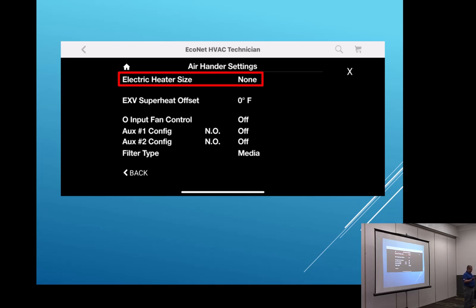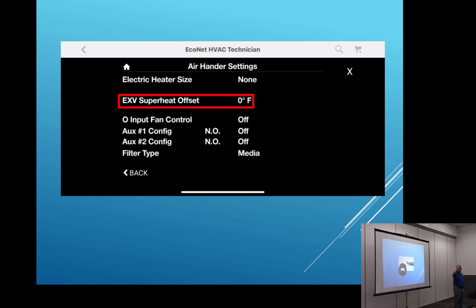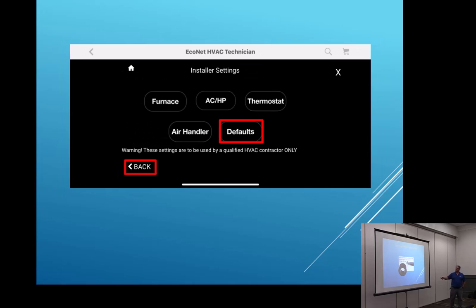We do have some updates out there that we'll go over a little bit later. The heat doesn't come on when you put in this new air handler. That's because the fan motor speeds did not get programmed in some of the boards for the heat mode. So we're going to show you how to reprogram that board later on to take care of all of that.